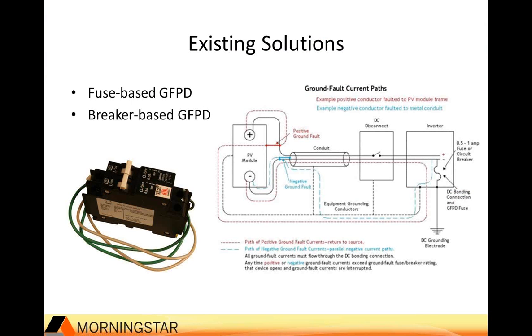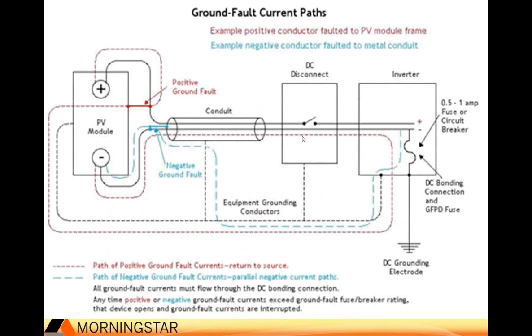So if you're familiar with existing solutions, usually how ground fault protection is done is a fuse or a small breaker is actually located between the negative ground bond in an off-grid system. Okay, so to go to a bigger shot here, you can see that what we have is this fuse or breaker is located where the negative of the system is bonded to ground. This happens to be a grid tie system, but it's the same in all types of applications.